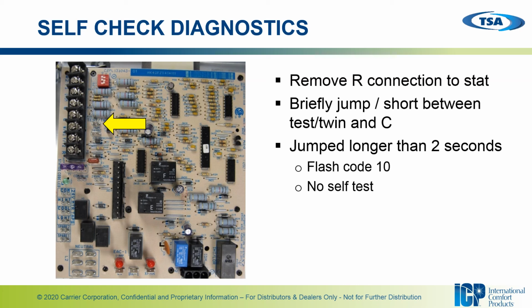And just like the variable constant airflow and the variable constant torque motors, the fixed constant torque furnaces also have a self-check diagnostic on the control board. All right, to use this feature, remove the R connection to the thermostat, briefly jump or short between the test twin and common terminals. Now, if you short them for longer than 2 seconds, the board's going to automatically fall out into a flash code 10, and it's going to ignore the self-test. Okay, so it has to be just a short, brief period that they're shorted together to enter the self-check mode.